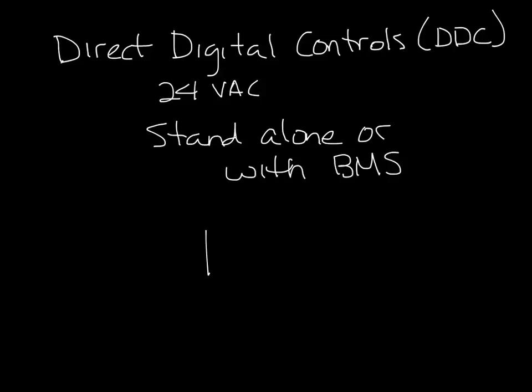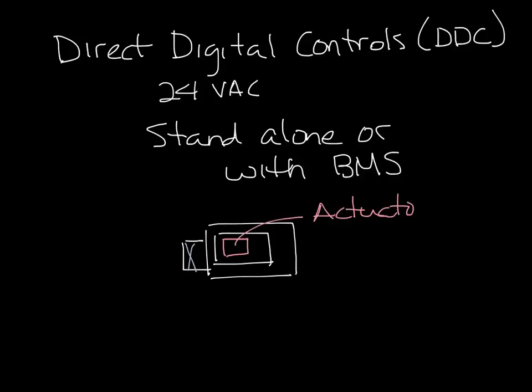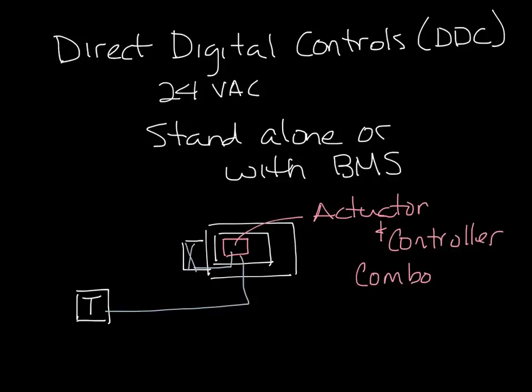So let's draw another single duct box. There's a flow sensor in the inlet, and then you have a controller-actuator combo usually. There are some models that are two parts, but frequently they're one combo unit now. And then a thermostat on the wall somewhere. Again, the thermostat is connected, and the flow sensor connected to the controller, which drives the actuator.